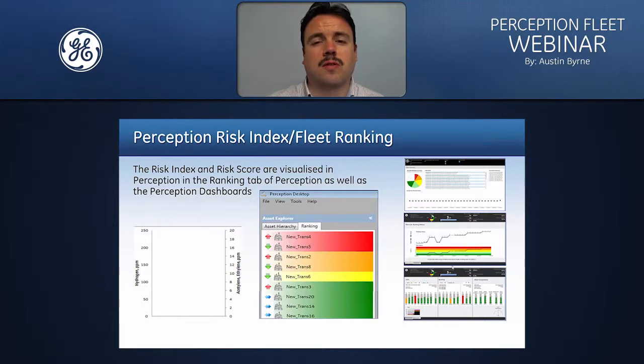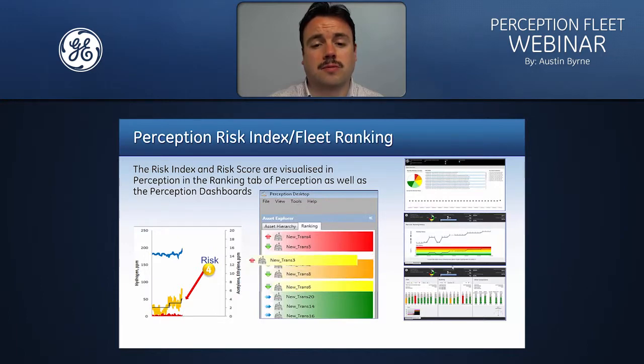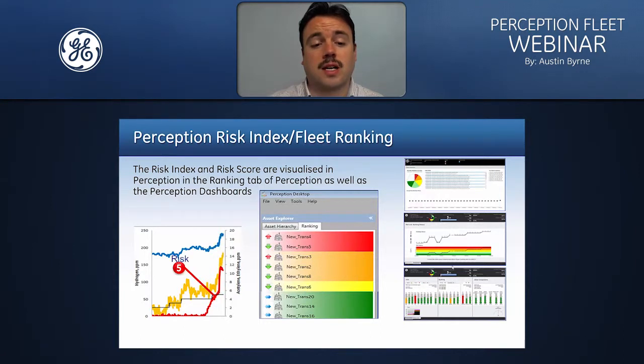So here we can see an example of how that would look in Perception. We have an asset that's measured over time, and you can see as gases start to increase, its risk index changes and it travels up the ranking table within Perception. So you can see right up until the acetylene levels push the asset into a risk index of 5. You can see on the right hand side the dashboards where we output this information in Perception, and we'll look at that in a little more detail later in the presentation. But we've tried to make those dashboards as simple and as easy to follow as possible, so you can identify exactly what's happening to the asset and what condition the asset is in, as well as how your entire fleet is performing.